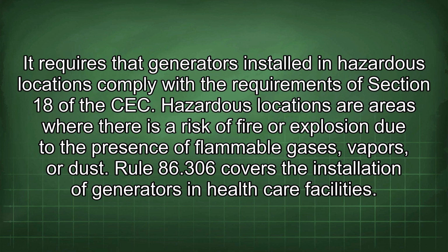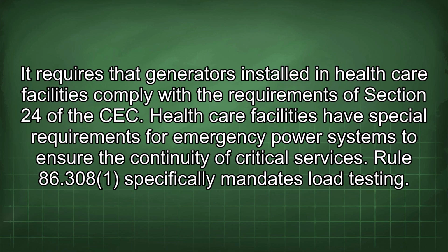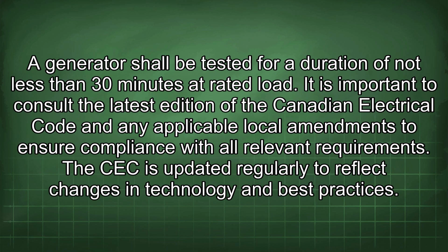Rule 86.306 covers the installation of generators in healthcare facilities. It requires that generators installed in healthcare facilities comply with the requirements of Section 24 of the CEC. Healthcare facilities have special requirements for emergency power systems to ensure the continuity of critical services. Rule 86.308 specifically mandates load testing. A generator shall be tested for a duration of not less than 30 minutes at rated load.